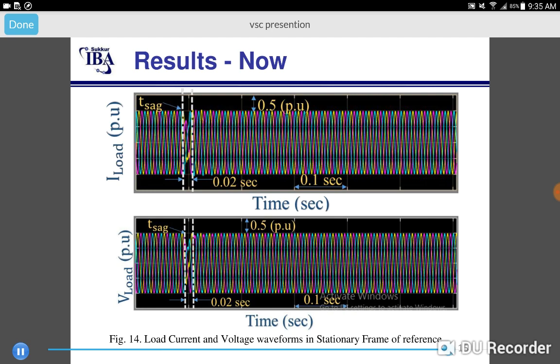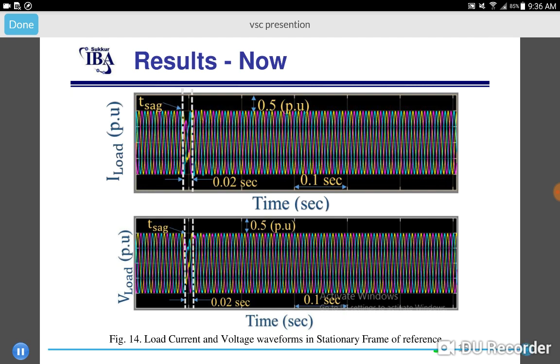So this current control voltage sag inverter inside the voltage sag compensator has successfully mitigated the transformer inrush current. And also, because the whole algorithm is being taken inside the stationary frame of reference, it has excluded all the need of additional heavy transformations. So this implementation is actually reducing the design complexities as well. So far these are simulation based results, and for the future work, we aim to generate the practical results and compare those results with this simulation and see the effects. So that's all about my presentation. Thank you.